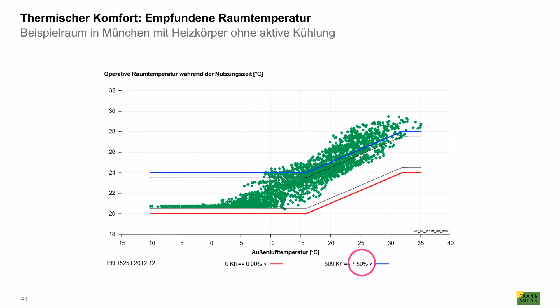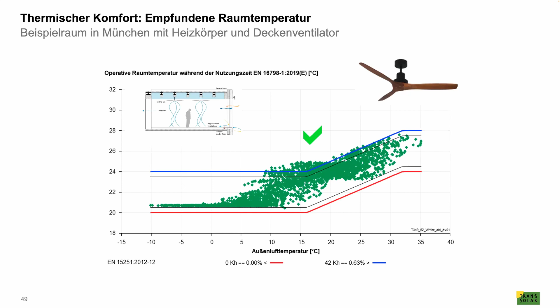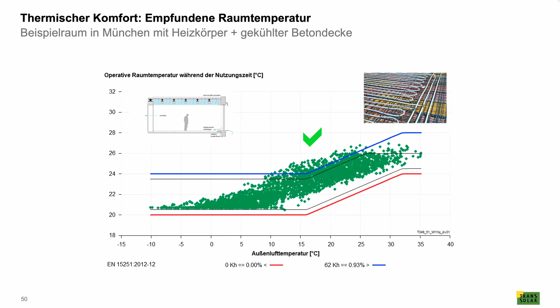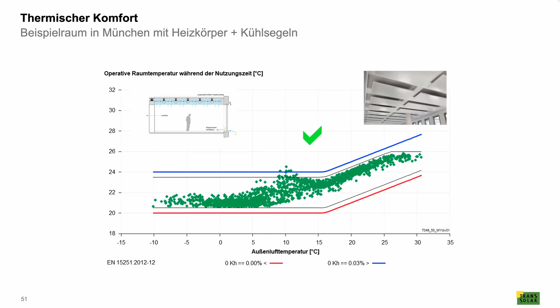So if you now integrate a ceiling fan, this is what happens. You're almost completely in the comfort range just by adding a fan. No air conditioning, no active cooling, same room, feeling comfortable and not feeling as hot. Although it's still 29 degrees, it just feels like 26. That's a similar effect to active cooling in the slab, where you need to put energy in to cool. Slightly better curve. If you have ceiling panels activated, this will be the performance. So replacing cooling by air movement is the simple idea.